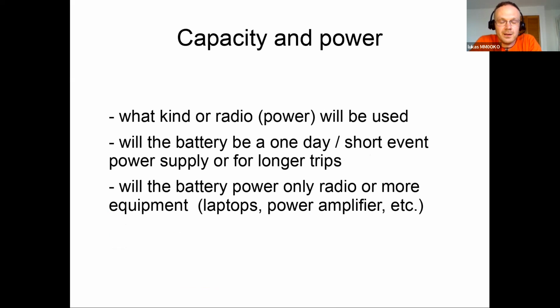Capacity and power: basically, that's a calculation of what power we need and how long we'd like to operate the equipment. What I'm usually doing is taking the maximum power the equipment will draw. For example, if a radio is designed for maximum power of 20 amps, just for a safe measure, I like to add 25-30% and calculate the whole battery for that higher output.